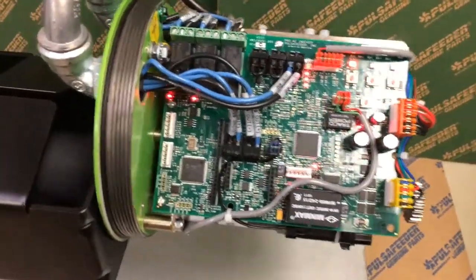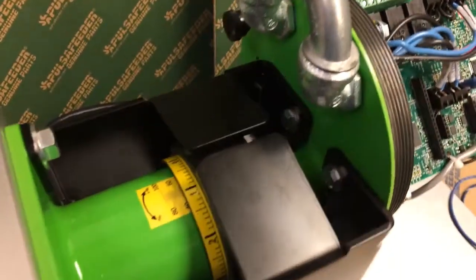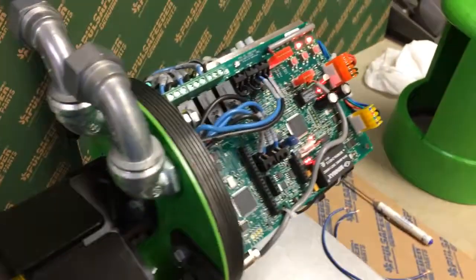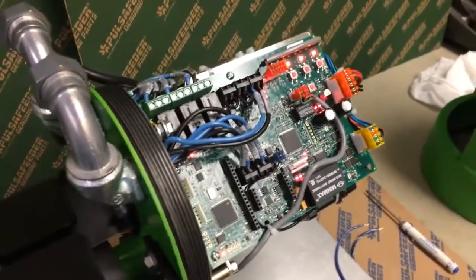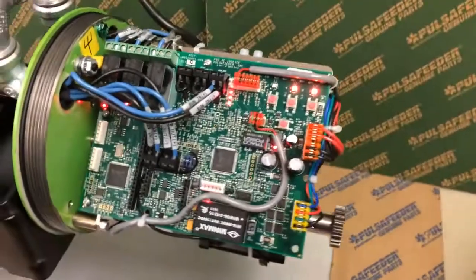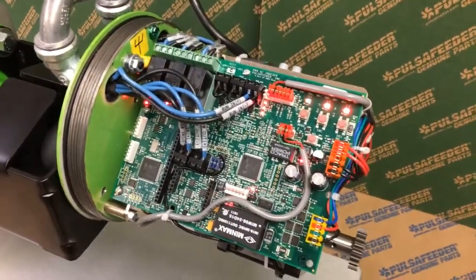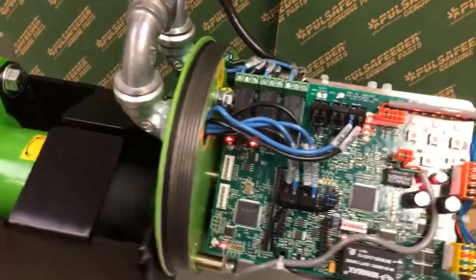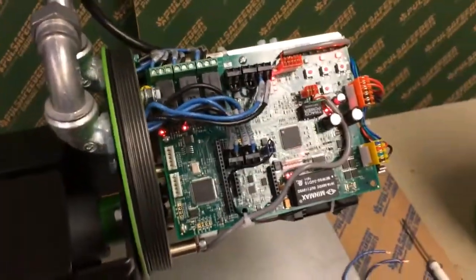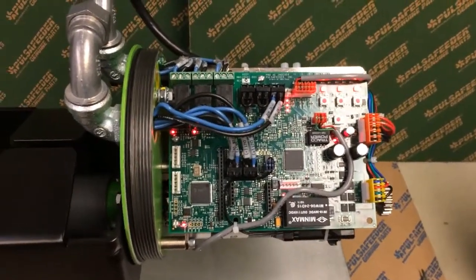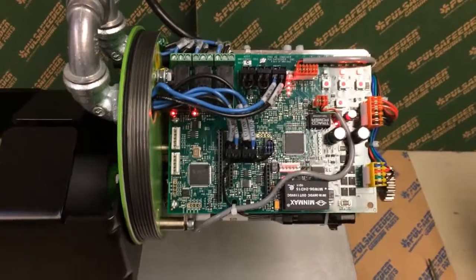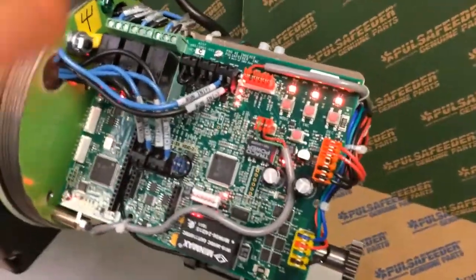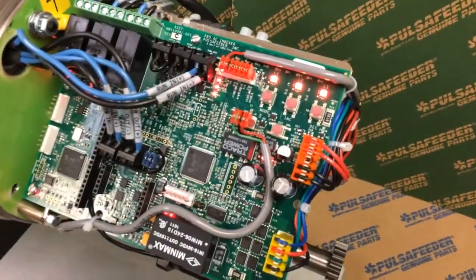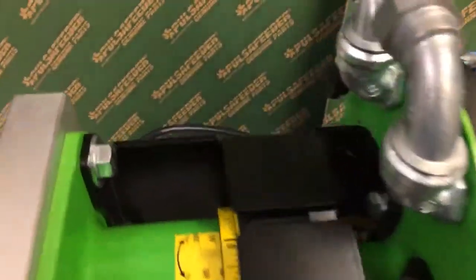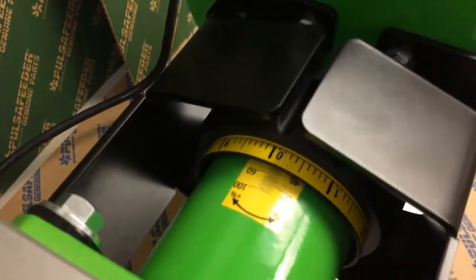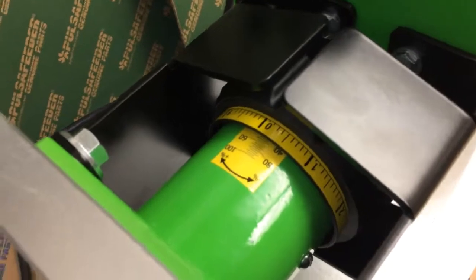The first thing the actuator does is it adjusts to a 50% position. So it finds what it thinks 50% should be in accordance with its measurement system. It really doesn't know anything about the pump yet, and it's saying, okay, I think this is about where the center is. That's important because when we couple the two together, they both need to know where they are. At this point, the actuator has found its 50% position, indicated by these two solid red lights here. But you can see over here on the pump side, it's pretty close to 50 because I've calibrated it once before, so it's not off very much.